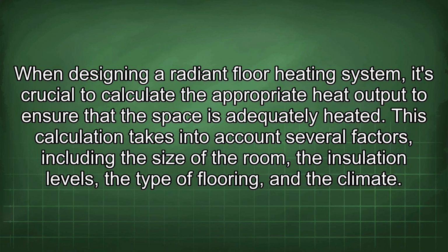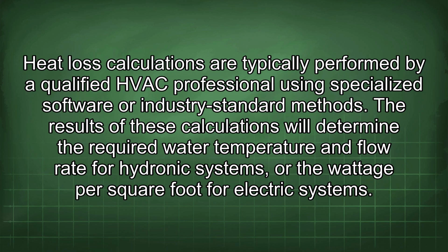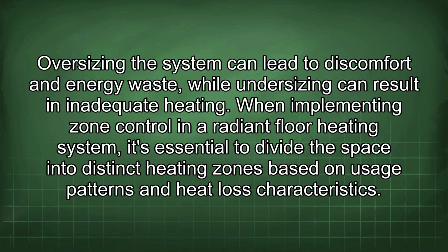subfloor. When designing a radiant floor heating system, it's crucial to calculate the appropriate heat output to ensure that the space is adequately heated. This calculation takes into account several factors, including the size of the room, the insulation levels, the type of flooring, and the climate. Heat loss calculations are typically performed by a qualified HVAC professional using specialized software or industry-standard methods. The results of these calculations will determine the required water temperature and flow rate for hydronic systems, or the wattage per square foot for electric systems. Oversizing the system can lead to discomfort and energy waste, while undersizing can result in inadequate heating.